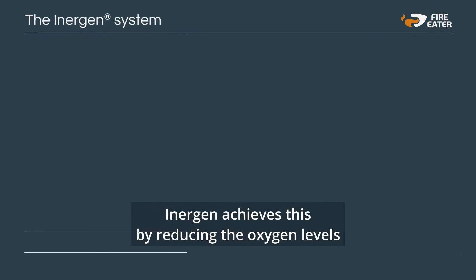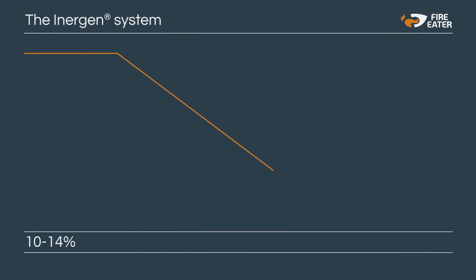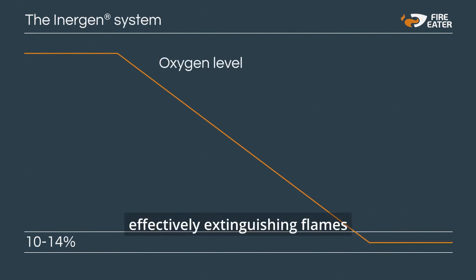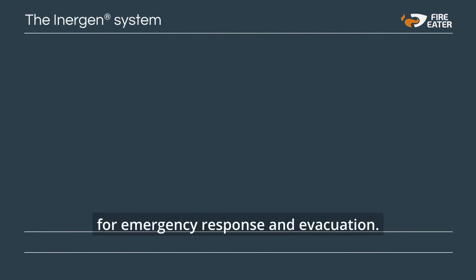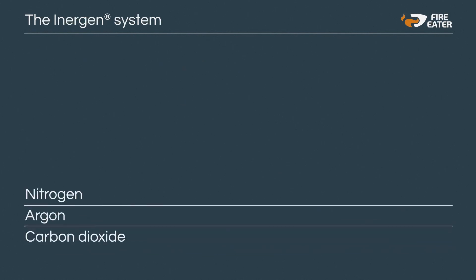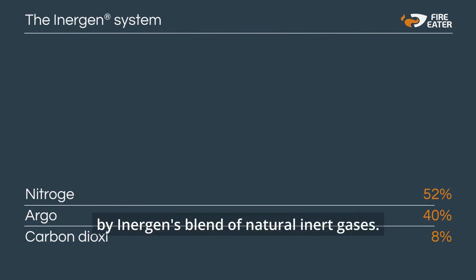Inergen achieves this by reducing the oxygen levels to between 10 and 14 percent — still within a safe range — effectively extinguishing flames while ensuring the area remains habitable for emergency response and evacuation. It's a delicate balance made possible by Inergen's blend of natural inert gases.